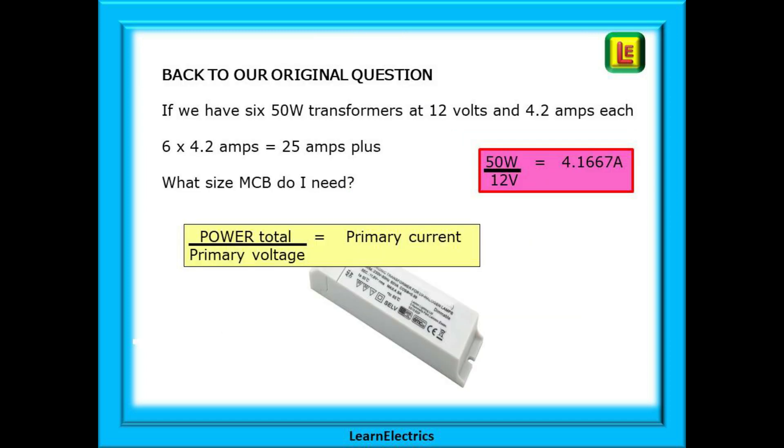Now, we can go back to our original question, the one that we started with. We have six 50-watt luminaires connected to six separate transformers, and each transformer output is 12 volts at 4.2 amps each, giving a total demand of 25 amps. What size MCB do we need on the input side?